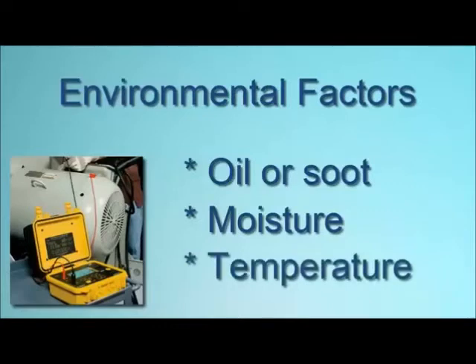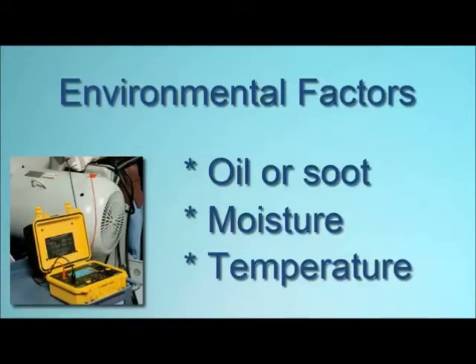Temperature is also an important consideration. Insulation resistance can vary with temperature, with different materials exhibiting different rates of change. Ideally, all resistance testing should be done at the same temperature. If this is not possible, temperature should be carefully recorded so correction factors can be applied to the resistance measurements.